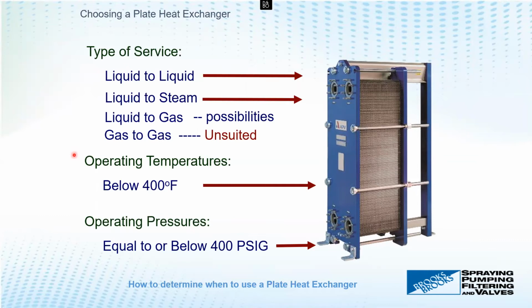And then we talked about the pressures and temperatures on that big chart that we had. Essentially, it's below 400 degrees Fahrenheit, is the way I remember it. It's really about 375 degrees Fahrenheit, but a 400 degree rule of thumb is if it's at or above that, we're moving out of elastomer gasket territory. It becomes tough to seal. And then for operating pressures, again anything at 400 PSI. So if we're below 400 and 400, we have liquid to liquid, maybe some steam, we're good to go. So plate and frames are alive.